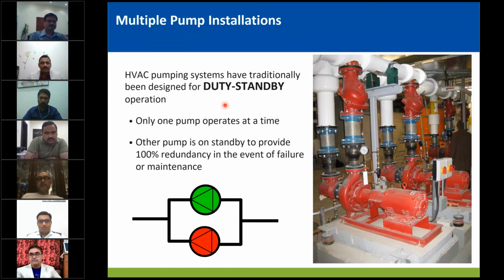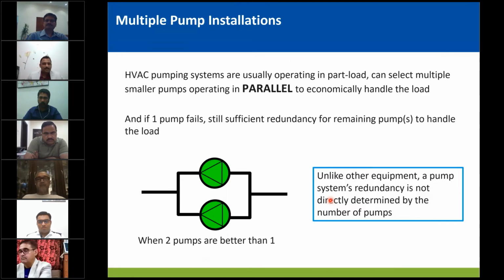Now, talking about parallel or multiple pumps and redundancy. Traditionally, we used to select pumps to be duty standby, which means 100% duty, and if the first pump fails, the second pump starts, delivering the 100% flow requirement. But redundancy for pumps is slightly different from other pieces of equipment. Unlike other equipment, a pump system's redundancy is not directly determined by the number of pumps. Let's understand this.